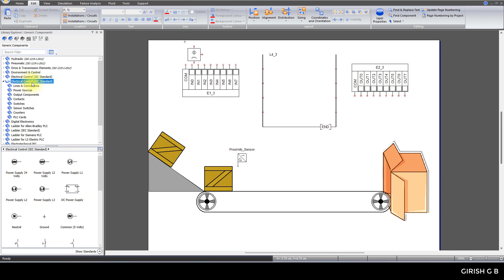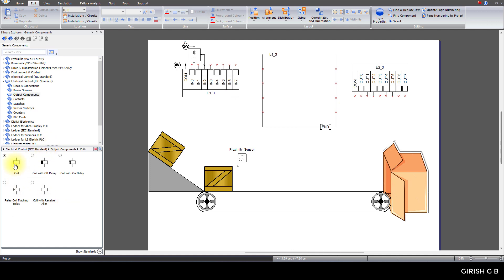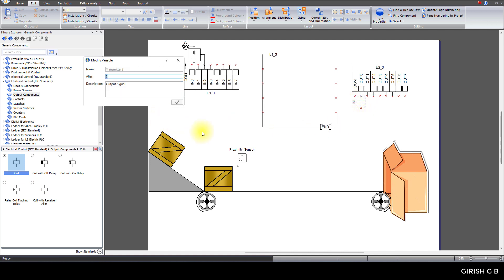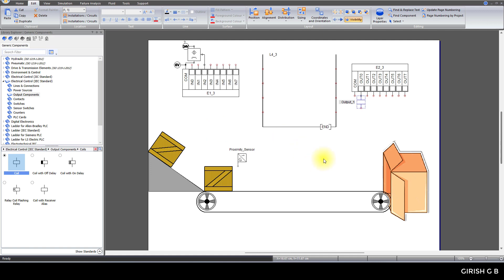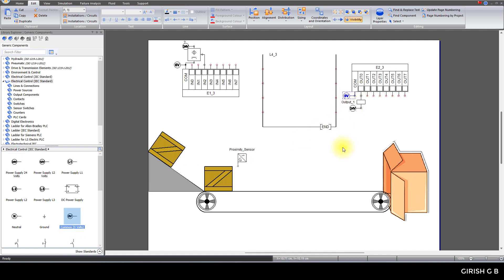From the electrical control IEC standard, the common is zero. For PNP, the positive and negative connections are made — the negative goes to zero common. I have a 24-volt power supply as the main supply. The input signal goes to an input — for example, input IN2 of the PLC. For output-related connections, we have output components. I will draw the output coil — output zero — and connect it. Power supply connections are also complete: 24 volts on one side and zero volts on the other side.